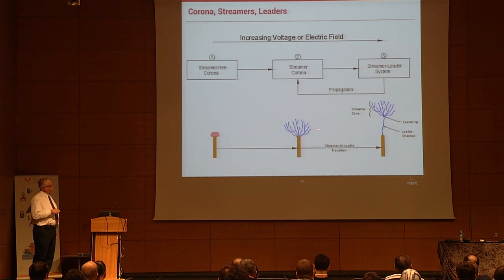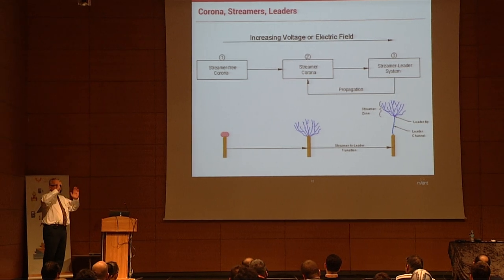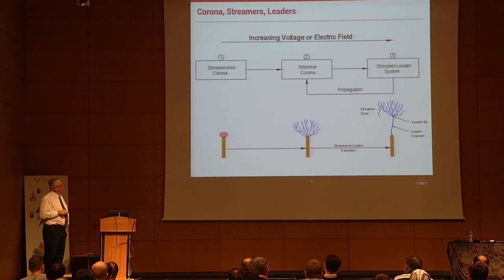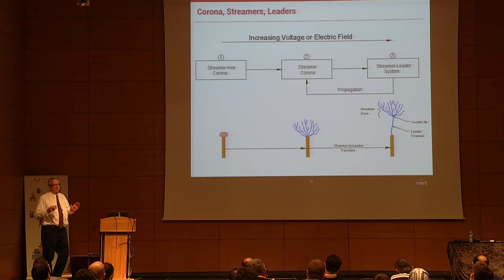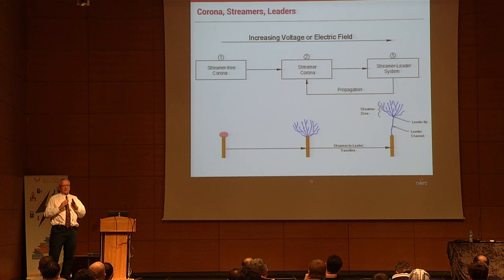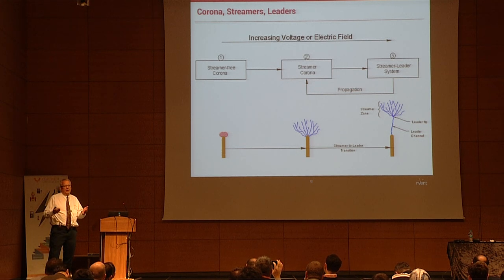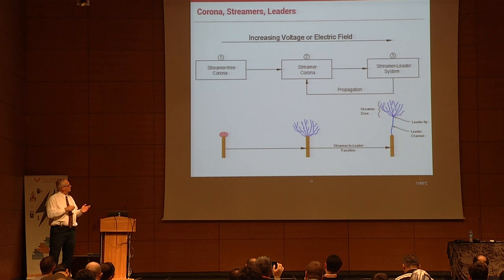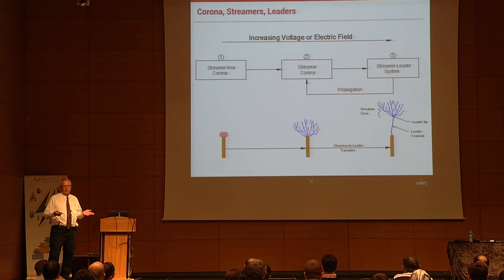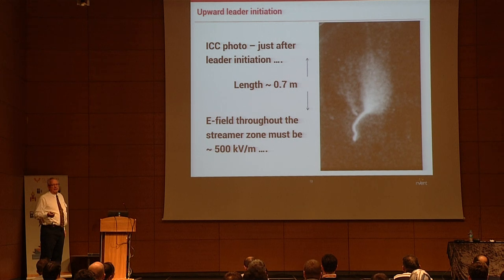The streamer-free corona eventually progresses to streamer corona, which starts traveling away from the terminal, forming a streamer zone with an upward leader. In many cases when the terminal is too sharp, the step from streamer-free corona to streamer never happens because the conditions aren't there. It's important that the lightning protection terminal is optimized so that this transition between streamer-free corona to streamer leader happens in a controlled fashion.